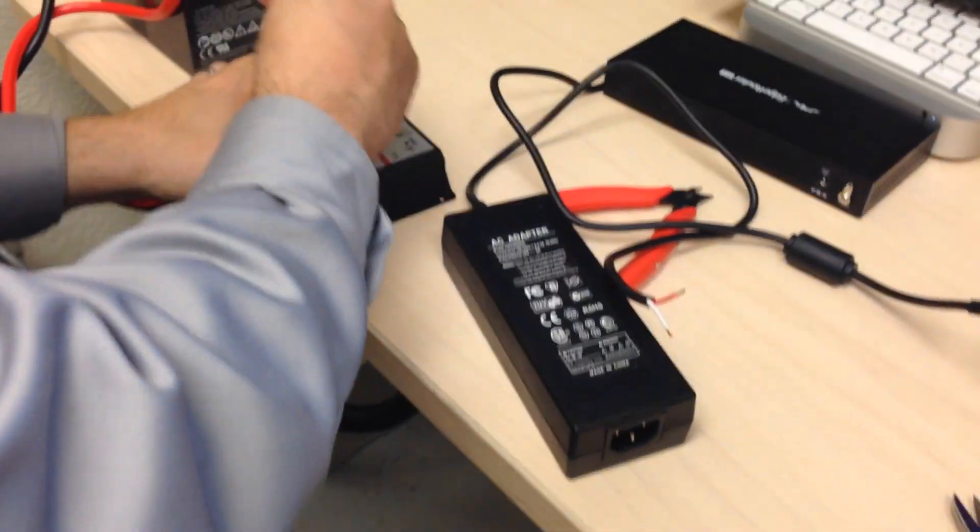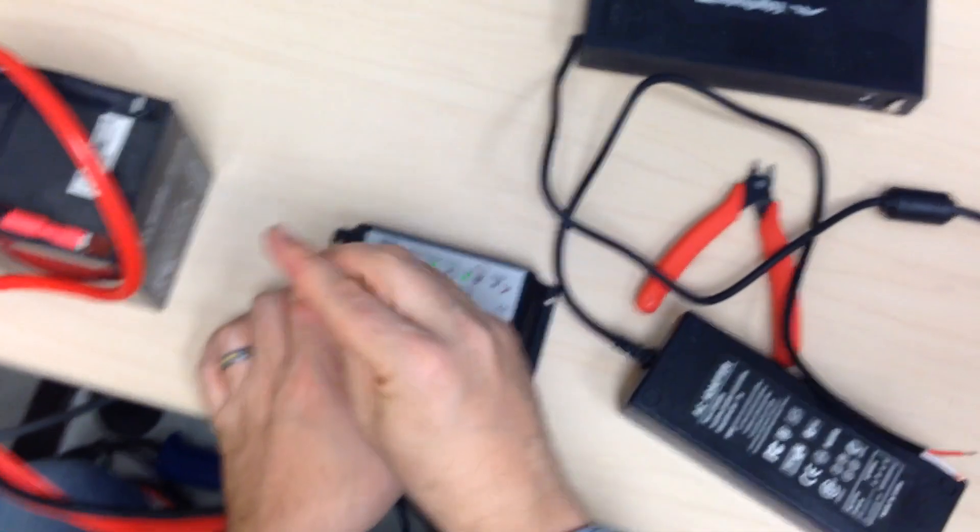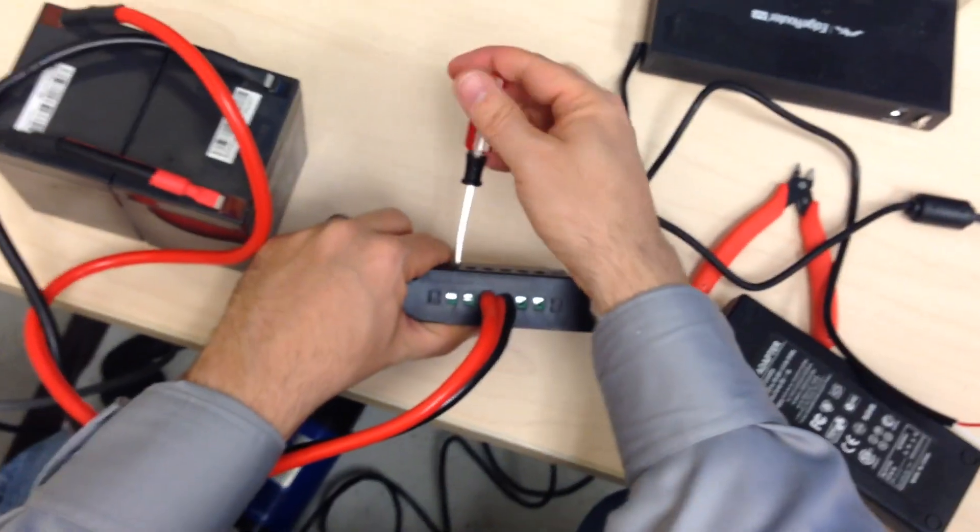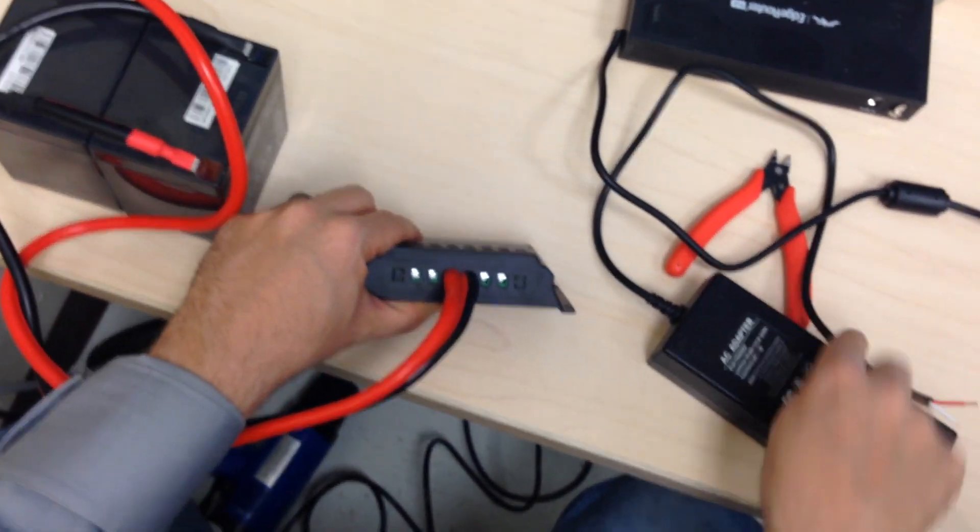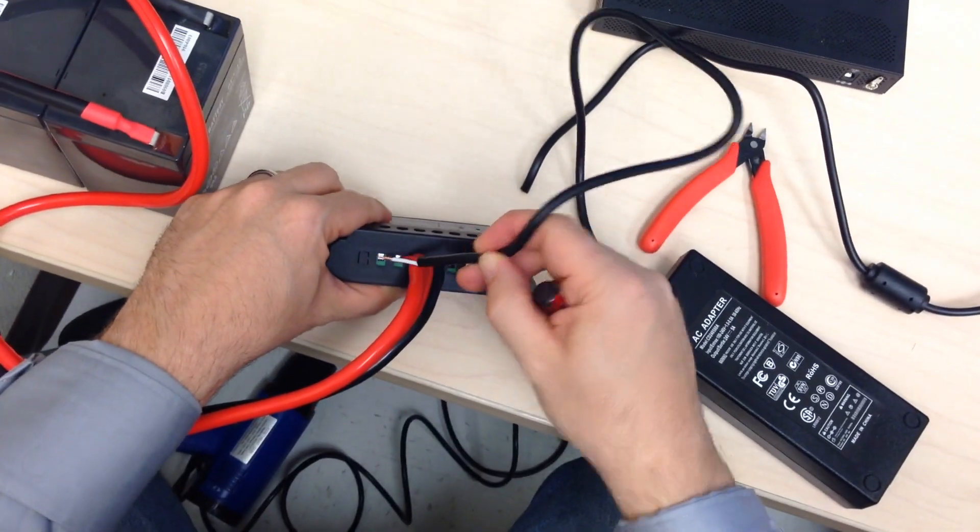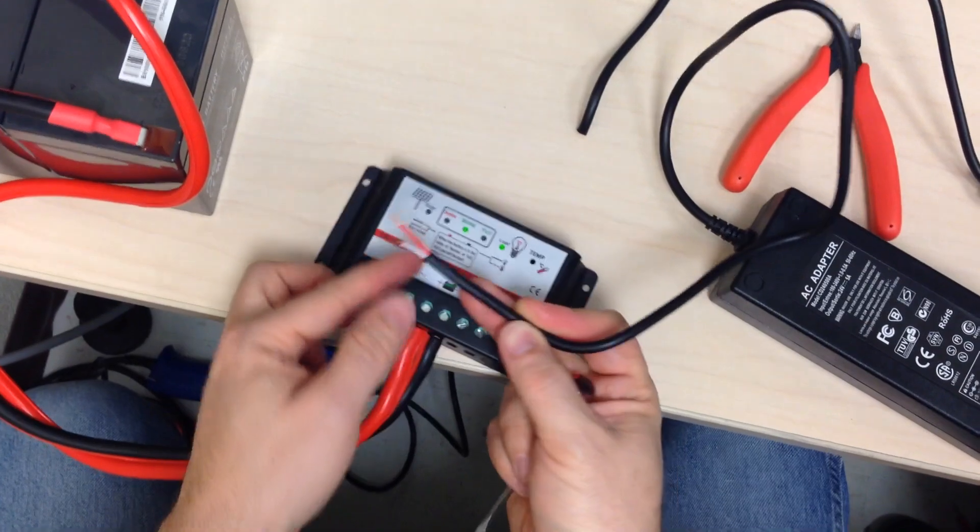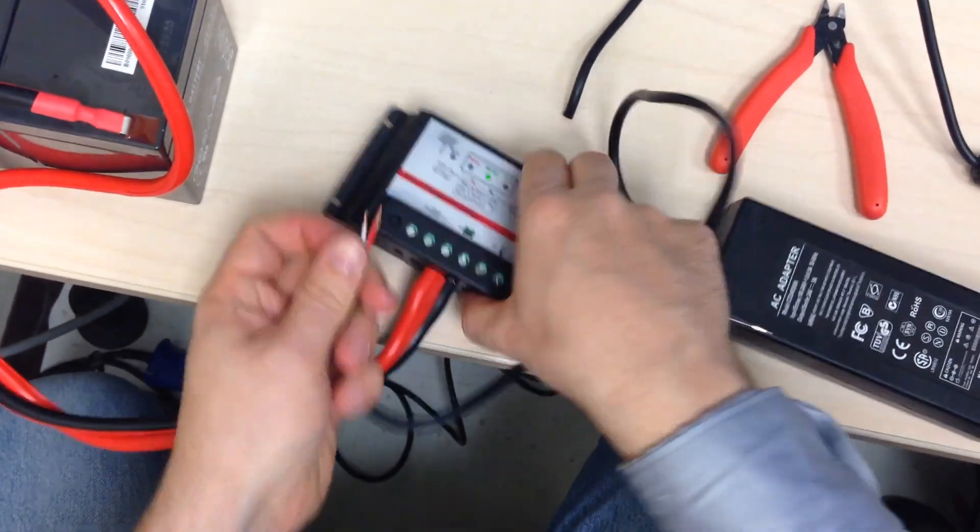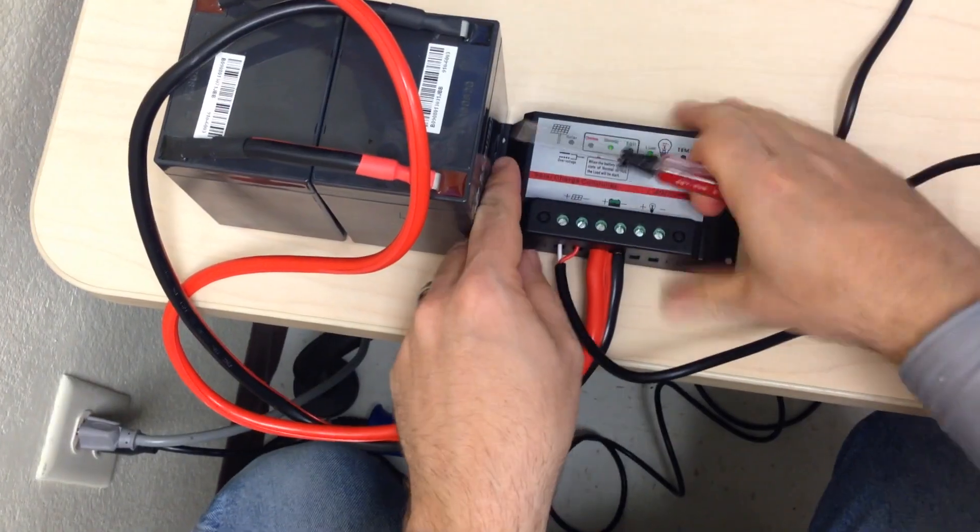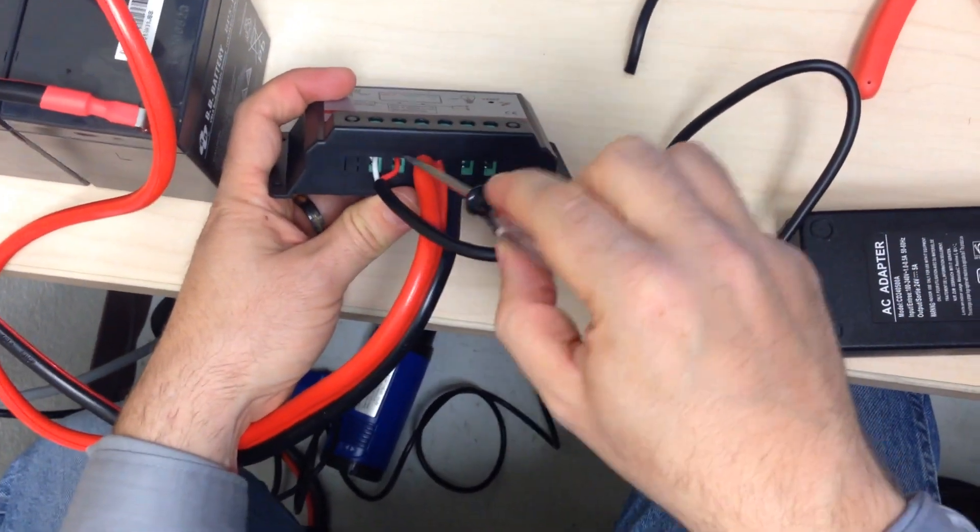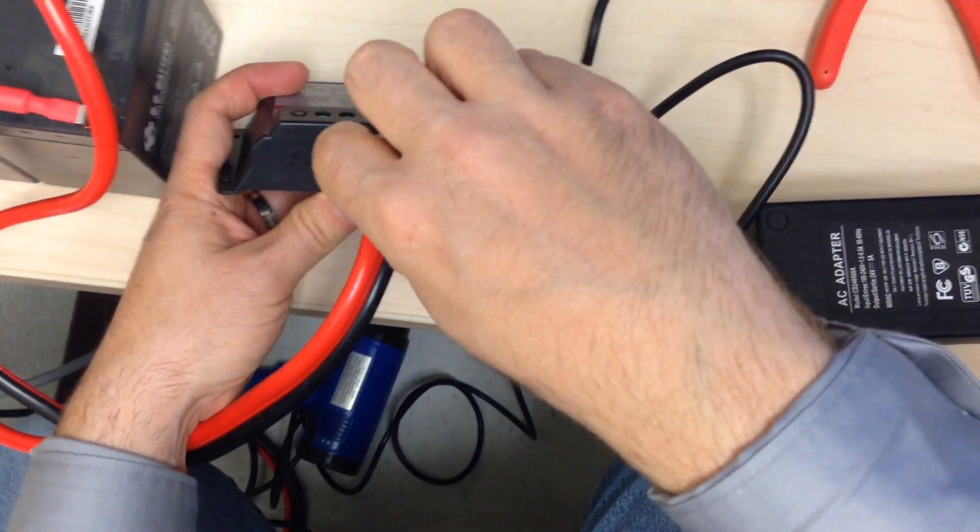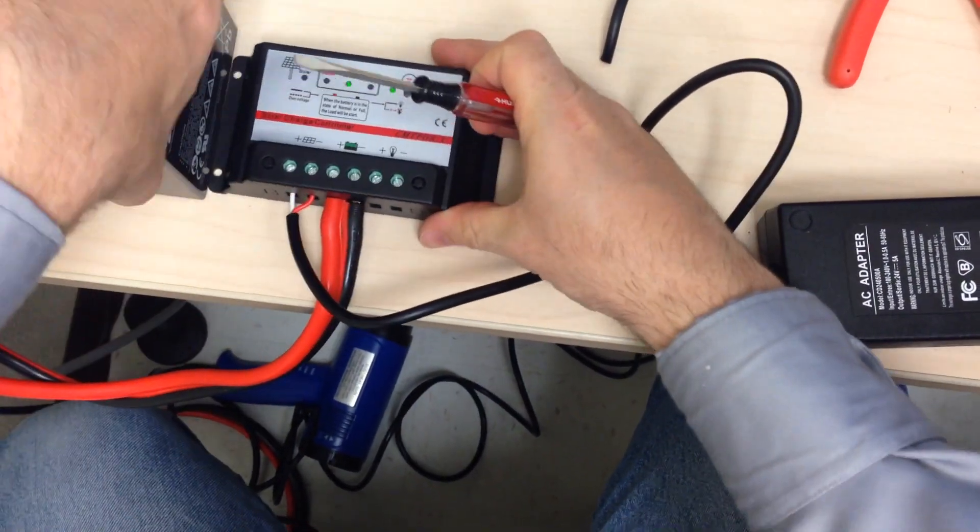Alright, I'm going to put this on the supply side here. Just loosen this up all the way. When you loosen these, it opens up that little compartment. Just want that open like that. Again, white is positive, which is odd, but we'll roll with it. Make sure these get down in there. These are small, so I'm not worried about them fraying out like those giant battery cables we put in. See there's no fray out at all, and the jacket goes right up to the edge. That's perfect. Just like that. No possible way that's going to short out.